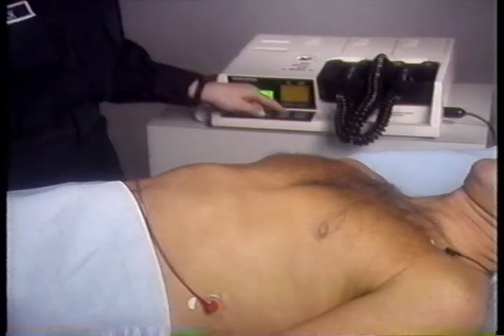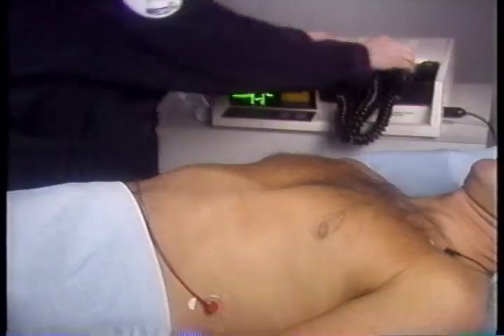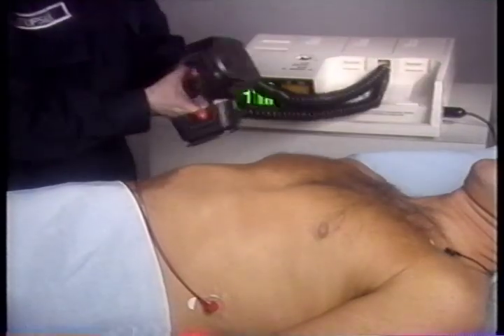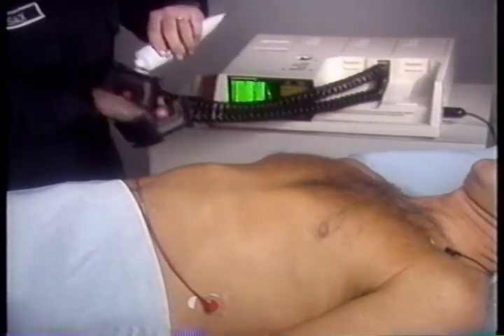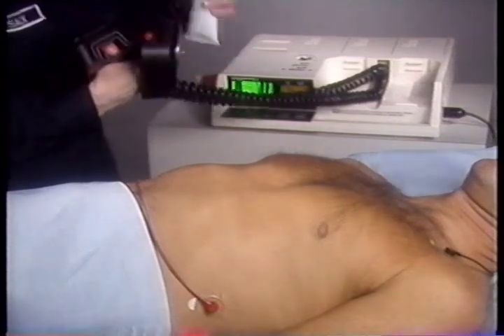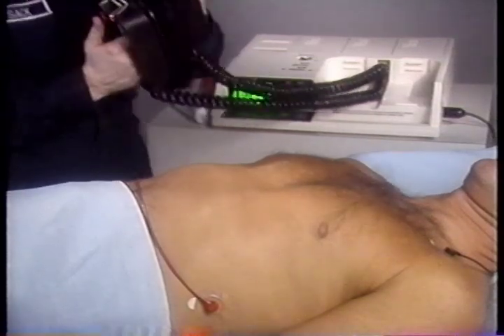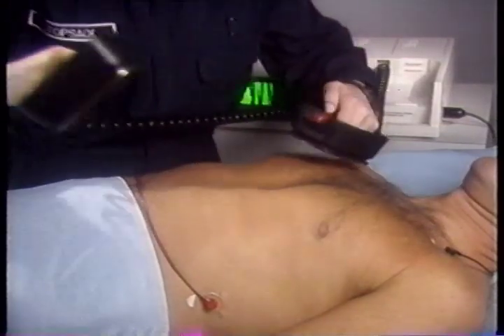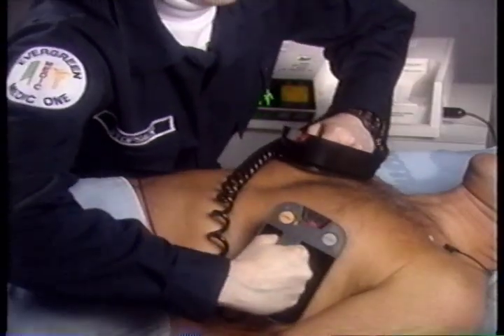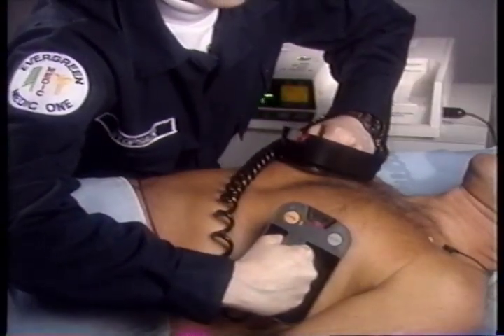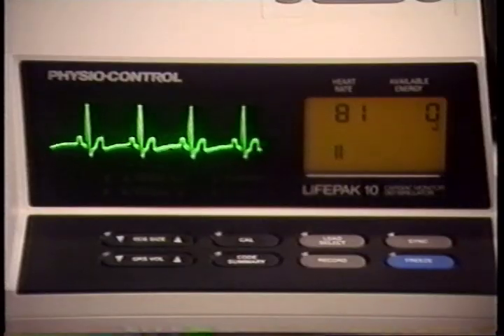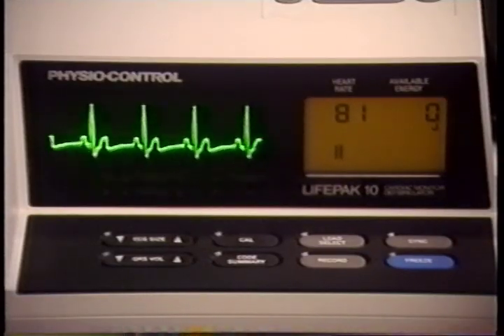To monitor through the paddles, you must place lead select in the paddles mode and apply defibrillation gel to the paddles. Place the paddles firmly on the patient's chest in the apex sternum position to obtain a lead 2 ECG signal. The monitoring control buttons are located directly below the cardioscope.